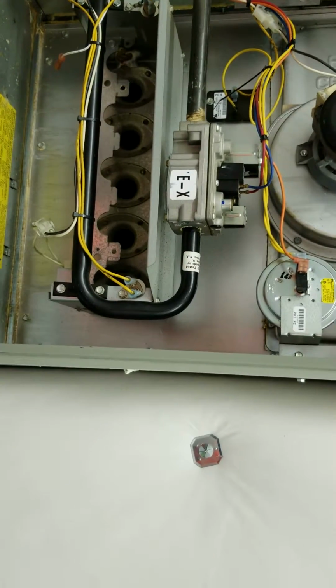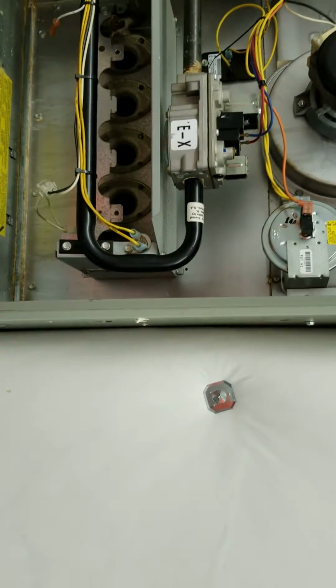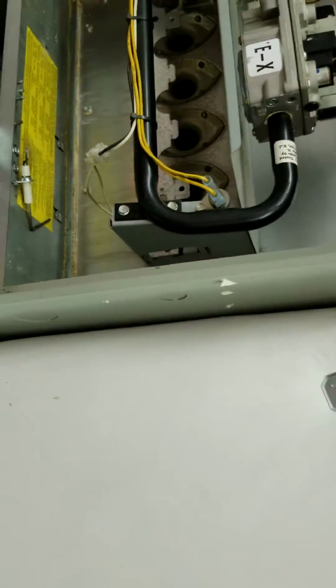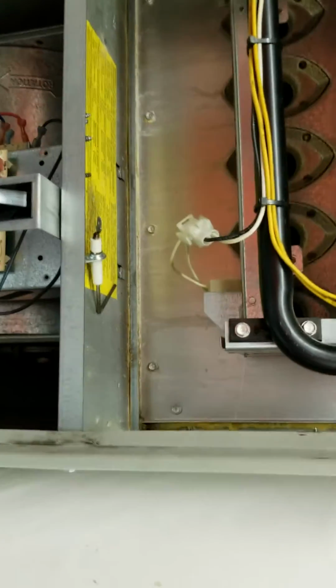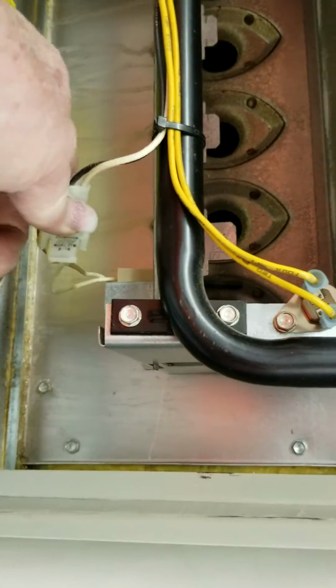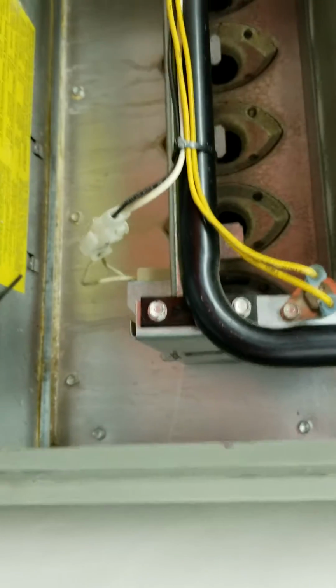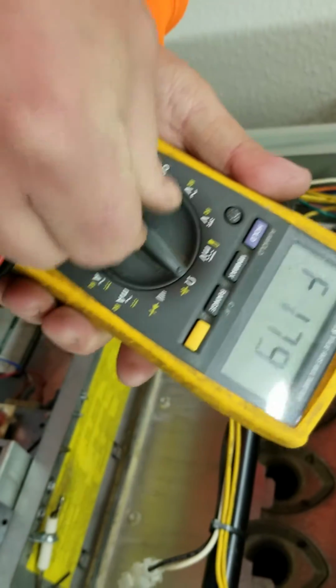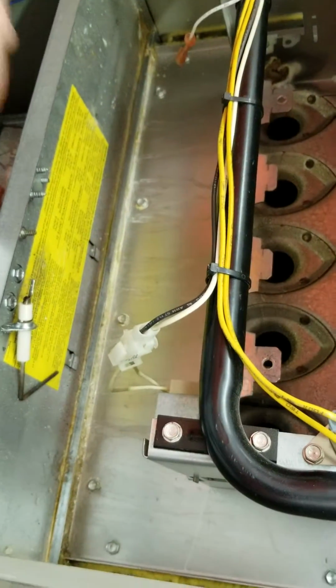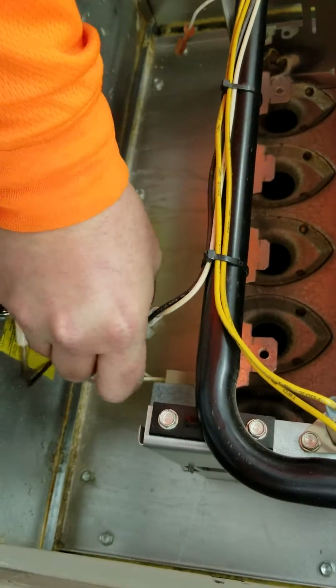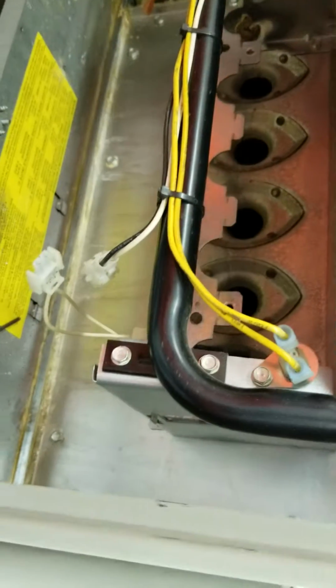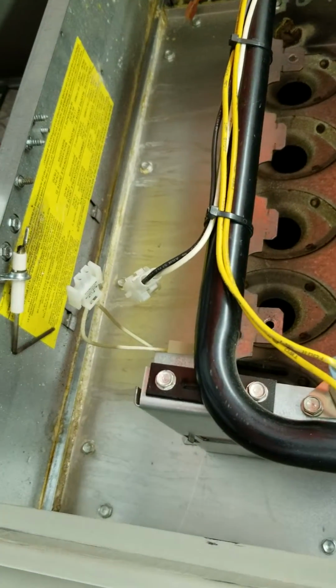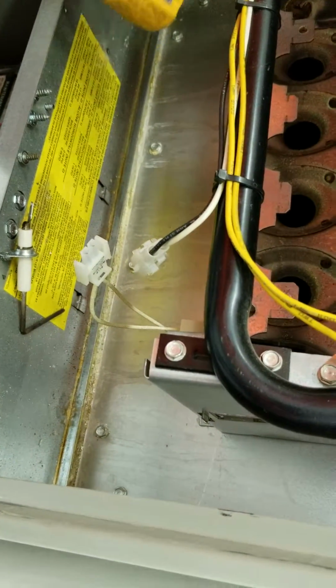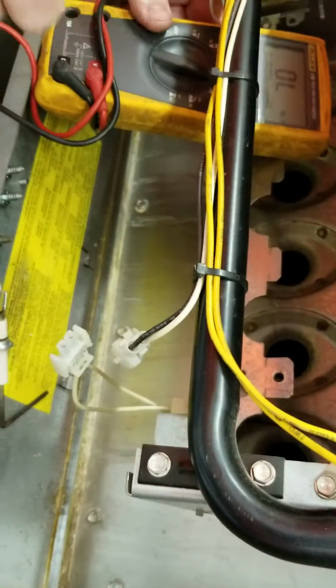Okay, now, next step, you're going to take your ohm meter and go here to this plug. That's the power to your hot surface igniter element. Go ahead and unplug it. Turn your meter to ohms. Unplug your sensor, or unplug your rod, and you're going to measure the resistance of that heater element. That's what it amounts to. There you go. That's fine.